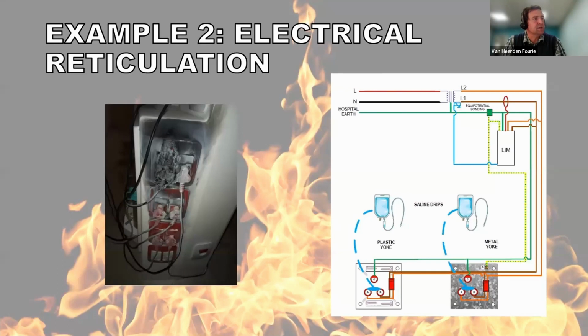So if you get the same scenario with a switch socket outlet with the metal yoke, then basically the metal provides a path for the current to the earth pin if there's a liquid spill, and it will alarm on the line isolation monitor. So it still won't take away the risk, but at least it will give you an early warning so that you can act timeously and resolve the threat.